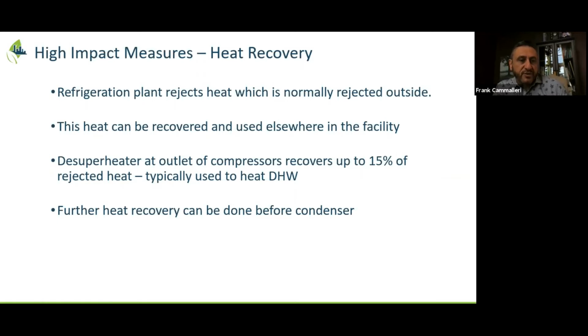Talk a little bit about the de-superheater. That's been used for quite a bit. It is used at the outlet of the compressors and recovers up to about 15% of the rejected heat. Typically this has been used in the past to heat up domestic hot water. And then there's also further heat recovery beyond that that can be done before the condenser, before you have to reject it outside. Again, we'll talk a little bit more about that in the next few slides.